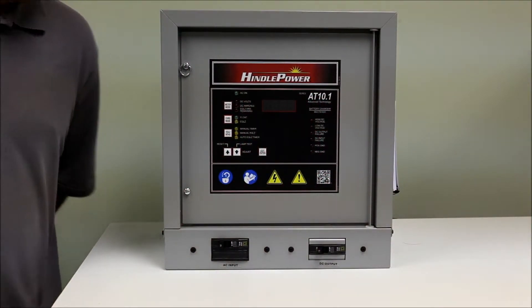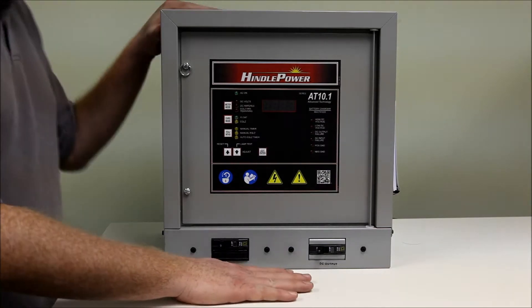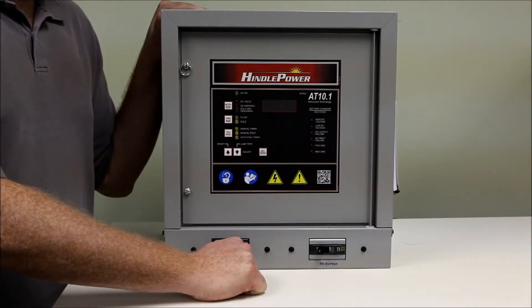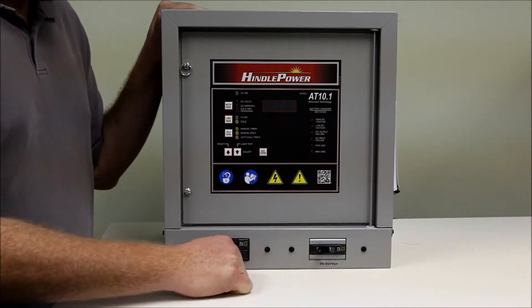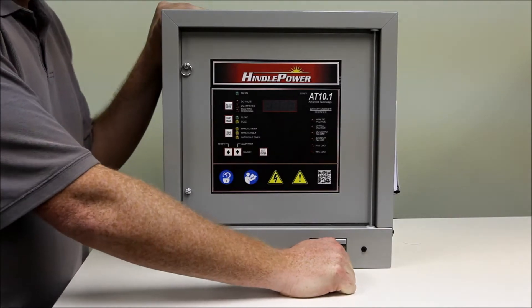Today we are going to replace the main control board on our AT10.1 product. For safety reasons we would like to turn off both breakers. The AC breaker being first, DC breaker second.